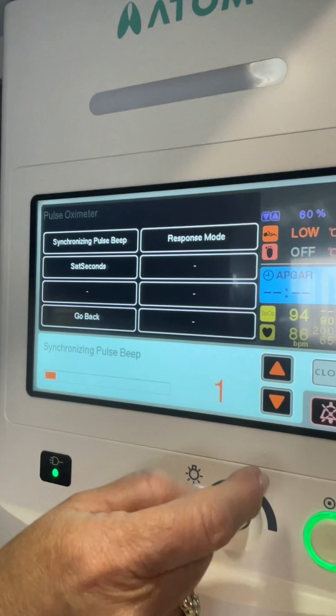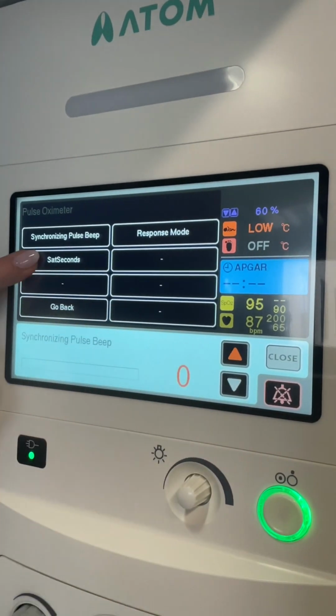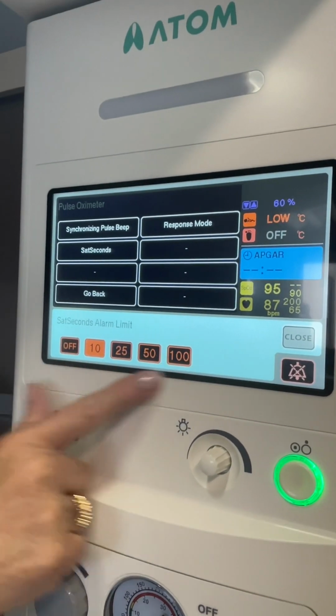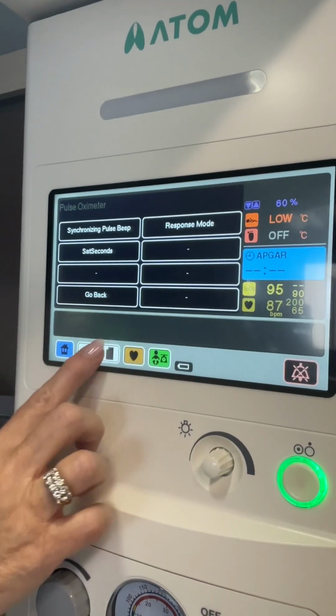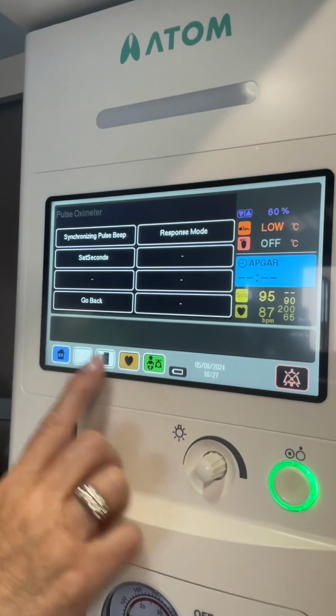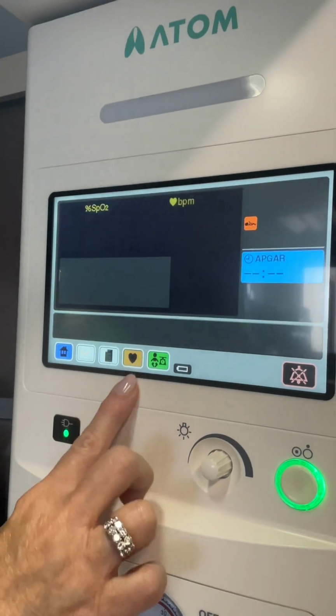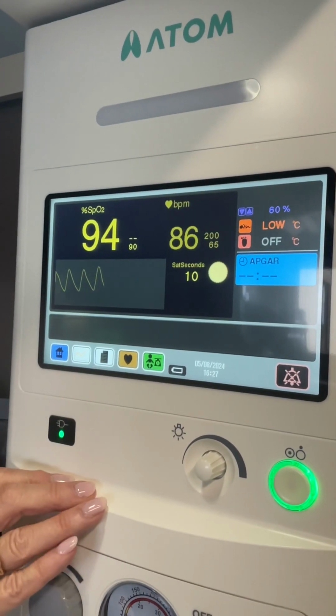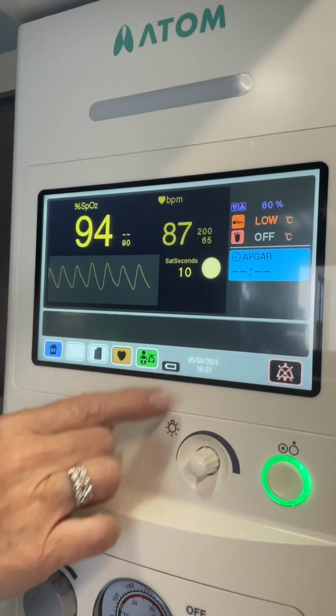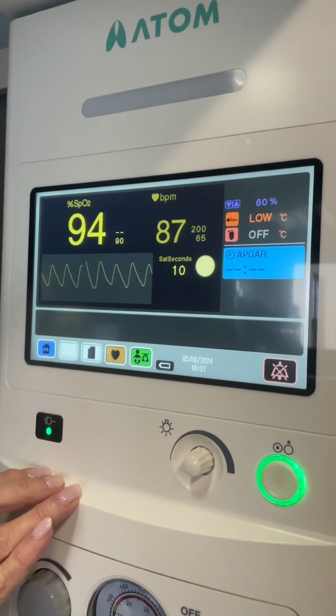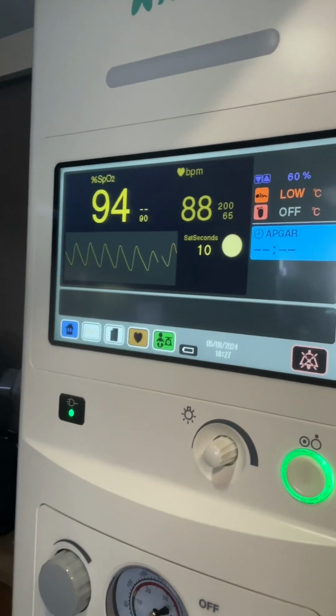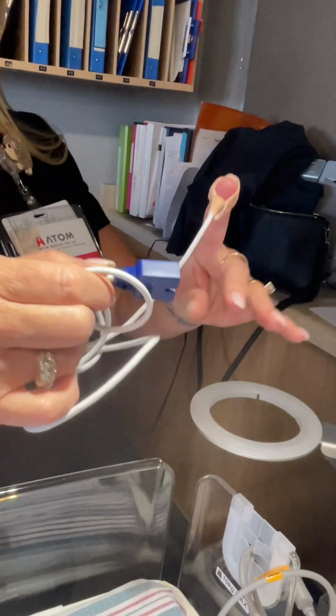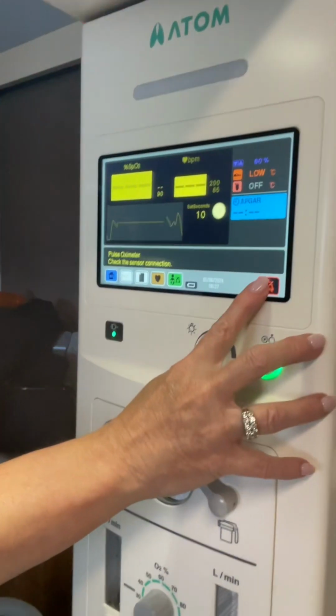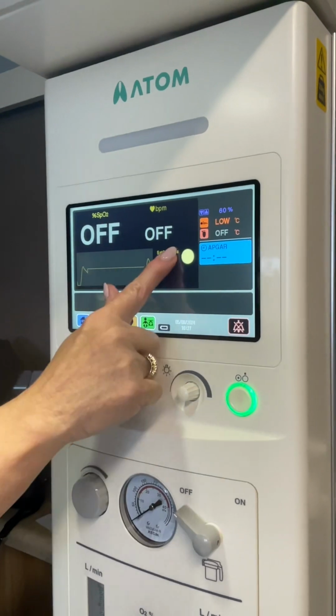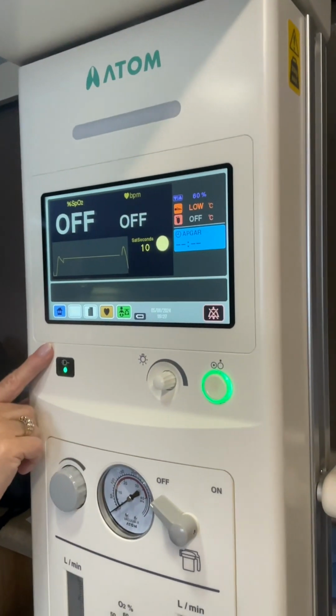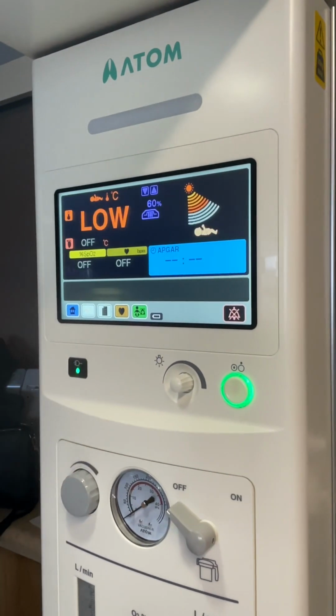I can turn on the beep if I want to hear it, turn it down, change the averaging time. Again, on this drop down or the menu bar at the bottom, if I select the heart, it brings the module of pulse oximetry out to the forefront so I can see my values larger as well as my pleth waveform. To turn off the pulse oximeter, you just separate the sensor from the cord and it'll alarm. I push alarm silence and it turns it off. Again, when I'm in a different screen, just push the house, it'll bring you back to the main screen.